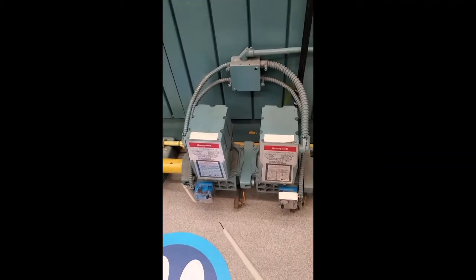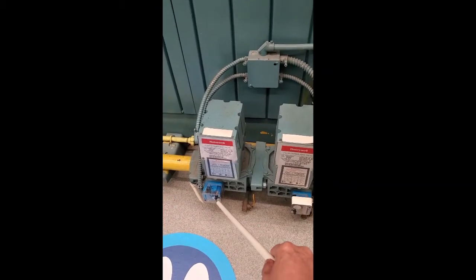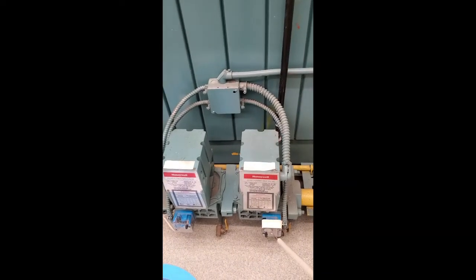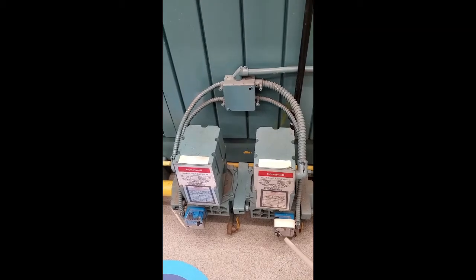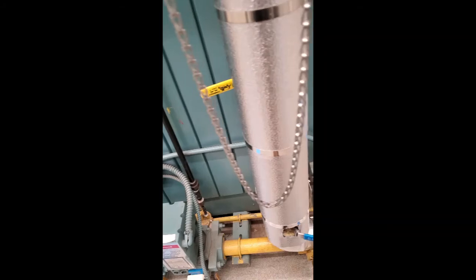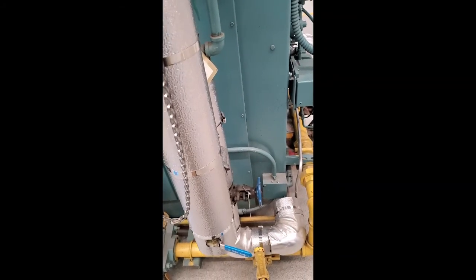This is a low gas pressure reset - the back button you can use. That's another reset - it's a high gas pressure reset right there. All those resets have to be okay, have to be made before you can start the boiler.